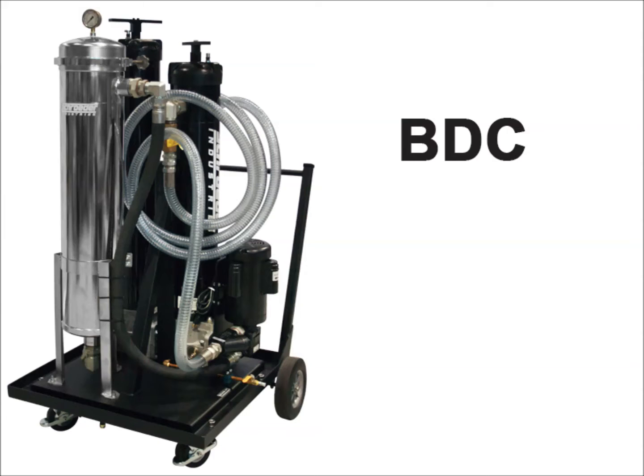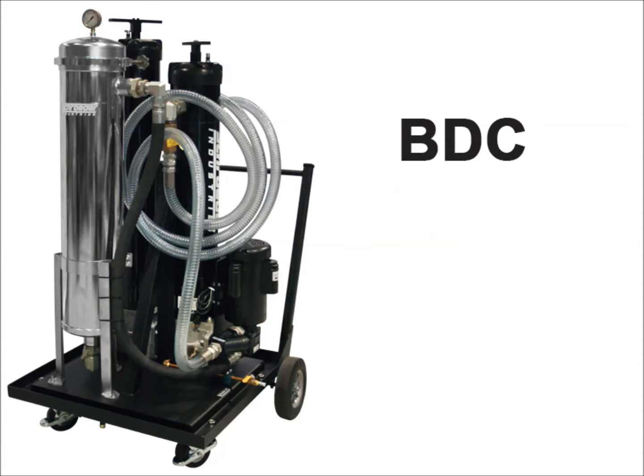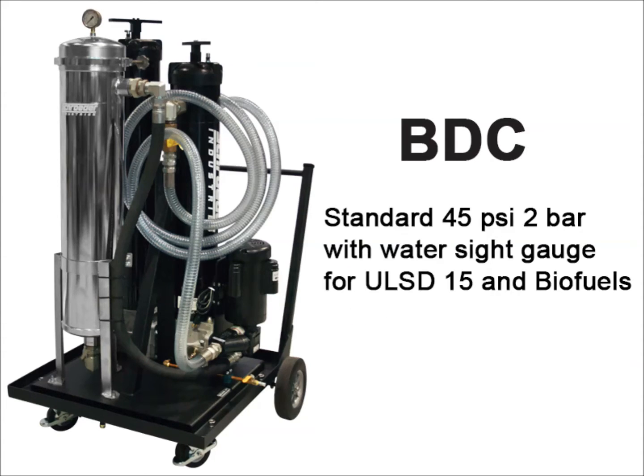The bulk diesel filter cart consists of new fuel/water separation media technology and a three-phase element construction for high efficiency, single pass removal of free water. This product can be used in single pass fuel dispensing or multi-pass reservoir cleanup and continuous maintenance. It can be applied upstream on the suction side or downstream on the pressure side of transfer pumps.